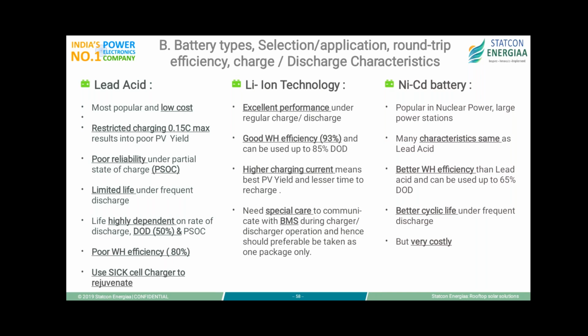The last point is very important: you need to be very careful with the design and power electronics used with lithium-ion batteries. This is because lithium-ion batteries are very sensitive, and due to safety concerns, you have to communicate with the battery. The charging and discharging controller, the PCU in solar cases, should understand the requirements of the BMS, hence communication is very important.